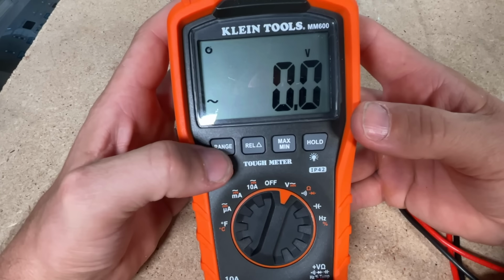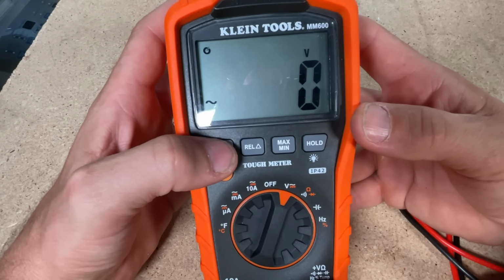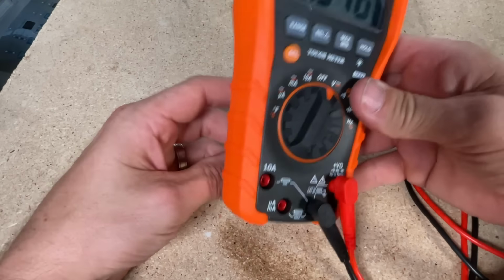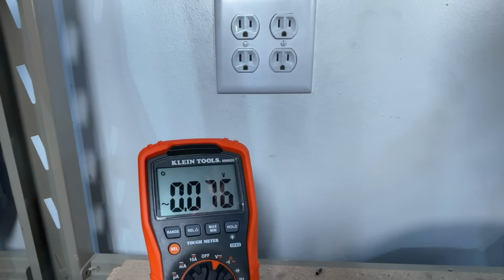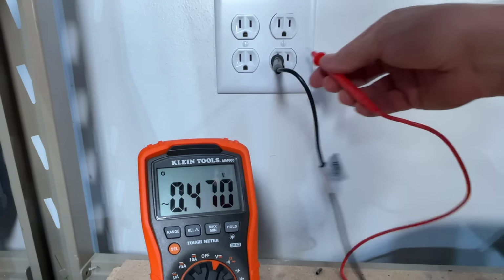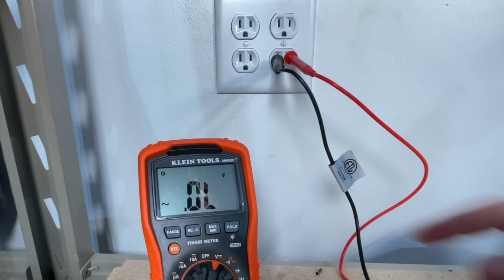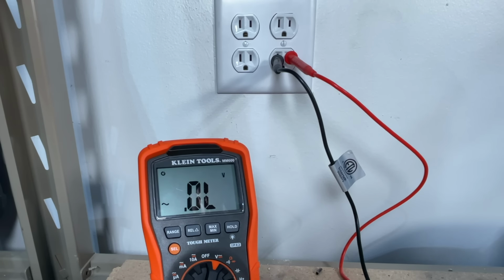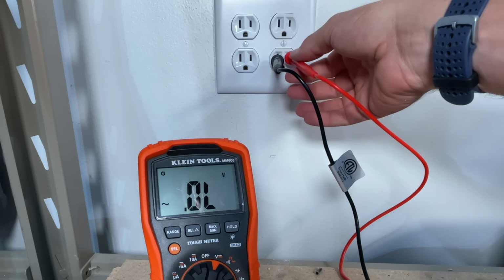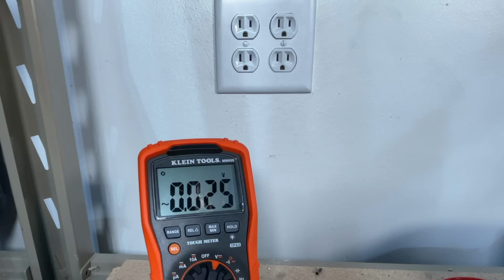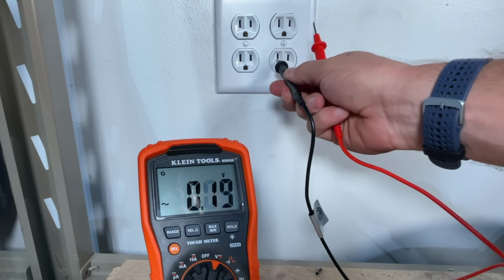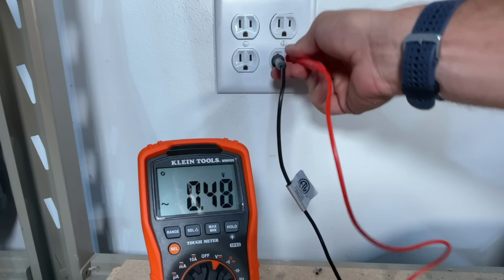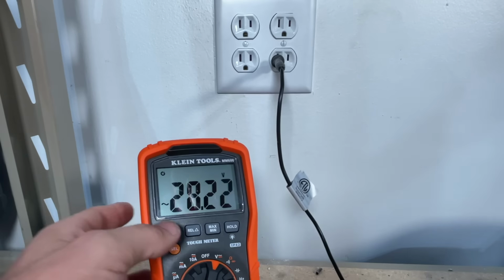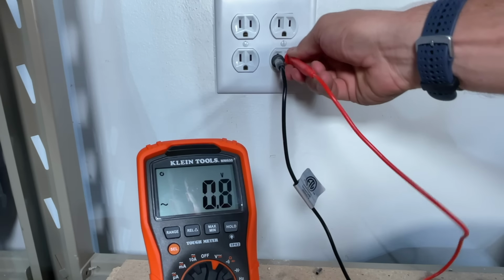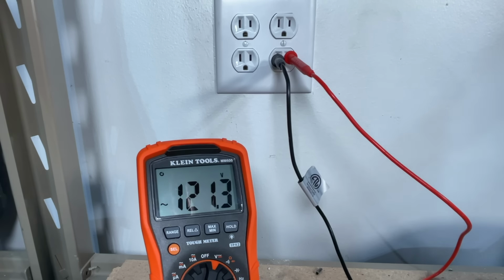If you try to measure 120 volts with the range set incorrectly, you'll see an OL, or outside the limits, error. Remember, always take the hot side off first. Even setting the range to 99.9 would still give an OL. Now we'll read out 121, so about 120.